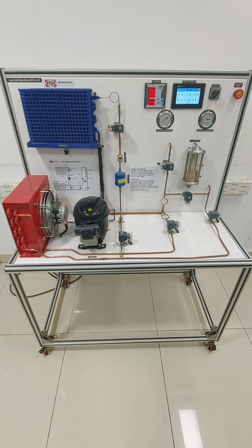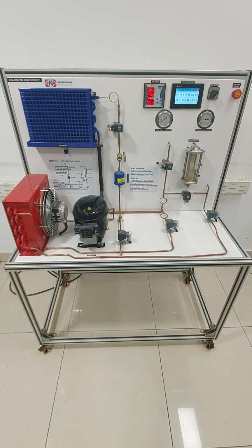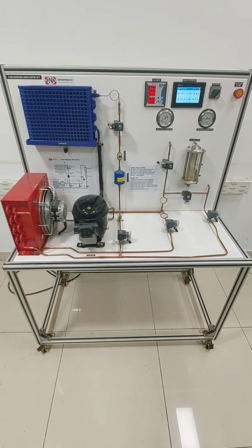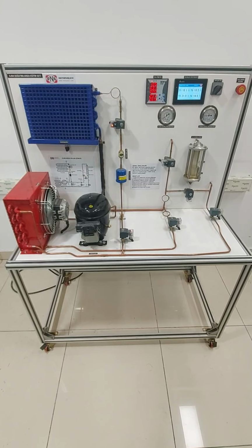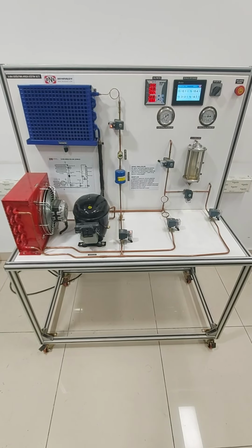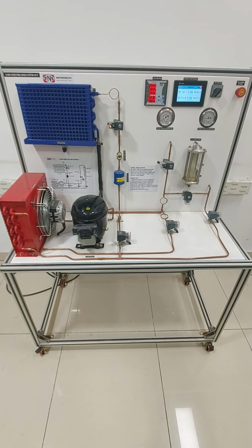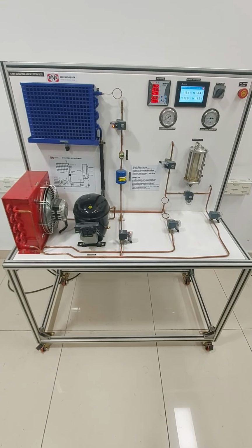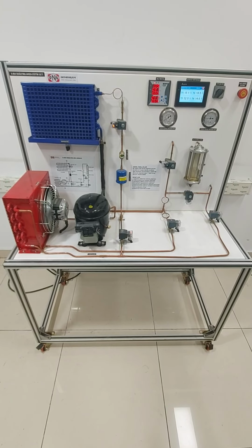Faults can be divided in two categories. The first one is hard failures, which either cause the system to stop functioning or not to meet comfort conditions. The second one is soft faults, which lead to degradation in performance but allow continued operation of the system. The development of these faults within vapor compression systems can result in significant increases in energy consumption.